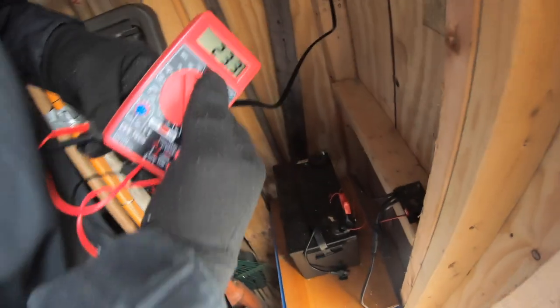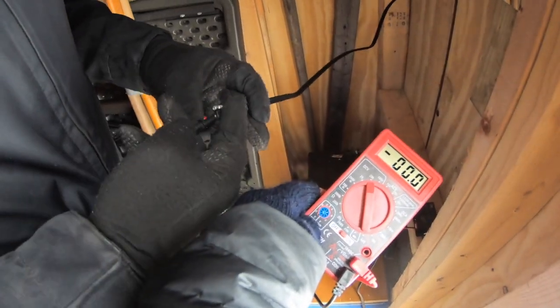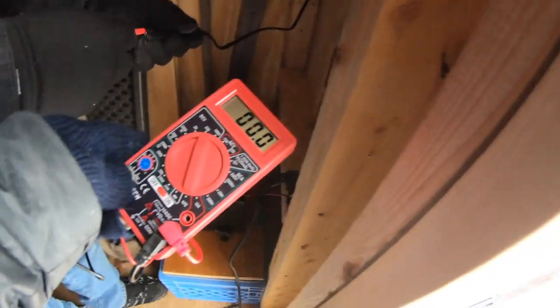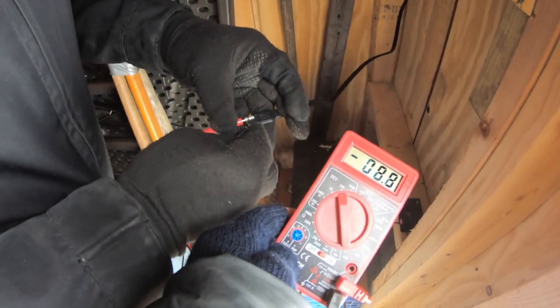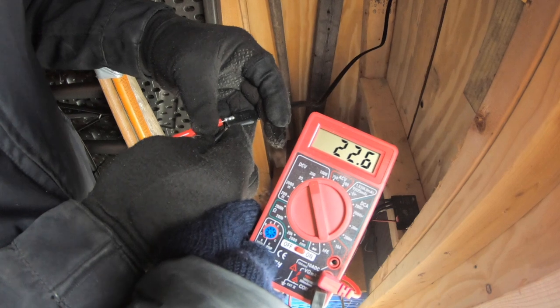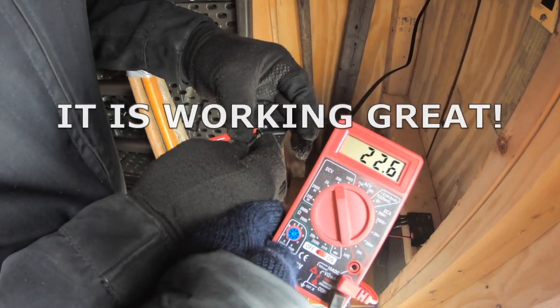20... hang on a minute. I can't keep it — hold this. I need more fingers. My gloves are slippery. I'll try one more time. You need the fingerless gloves. I'm too lazy to put them on. It's 22.8 volts, 22.6. So what does it mean — is it charging or not? It's charging, yeah. You're getting 22 volts out of this. It's exactly what it's rated for. Perfect. Even on a cloudy day. So even on a dismally cloudy day, it's still charging. That's the proof.